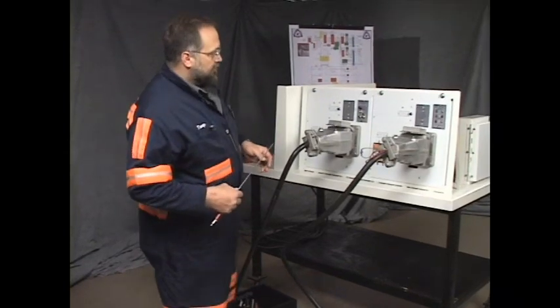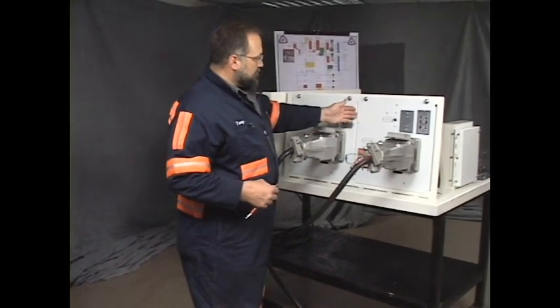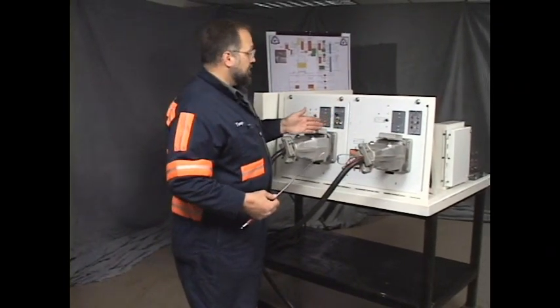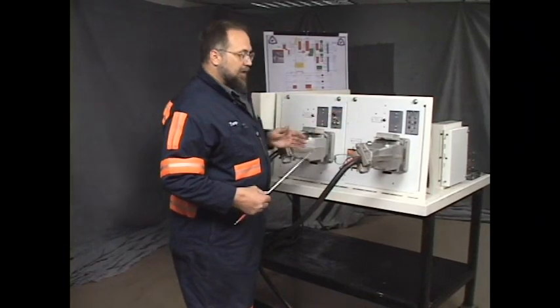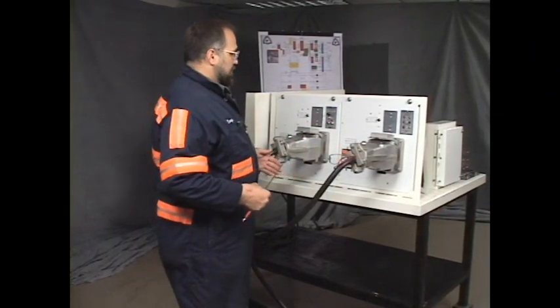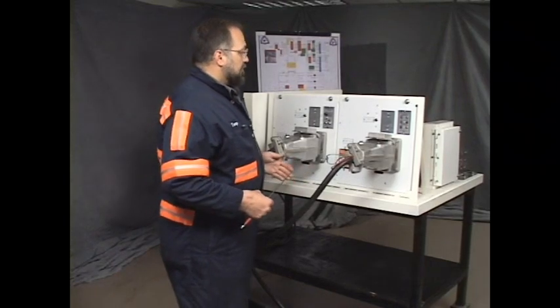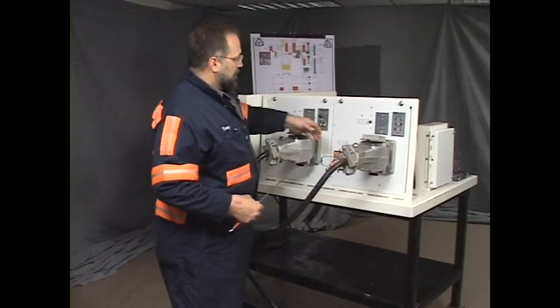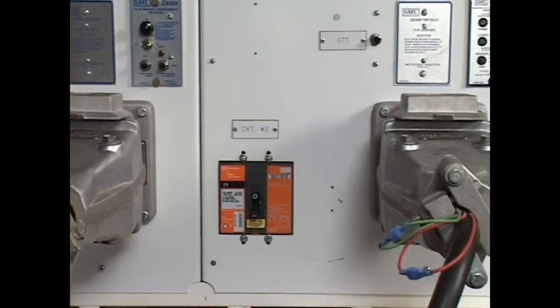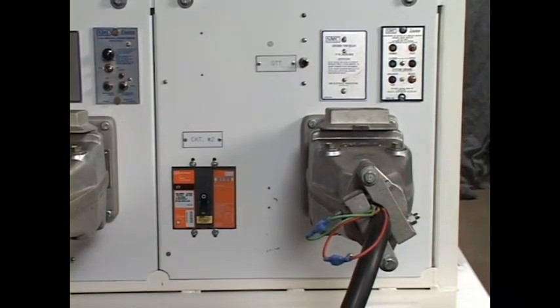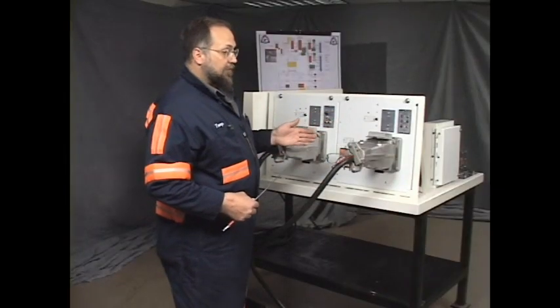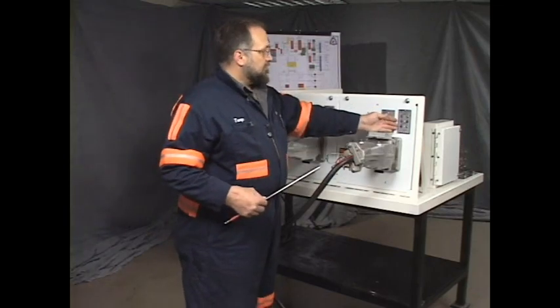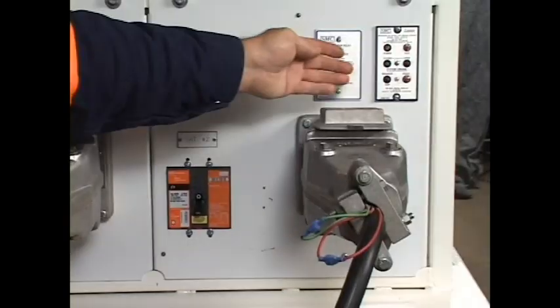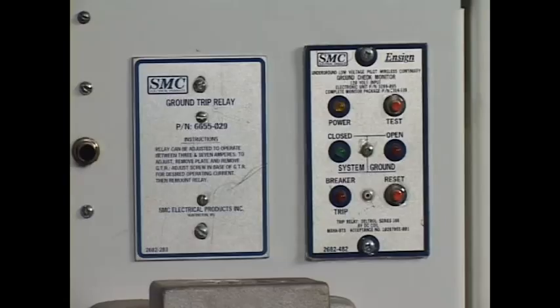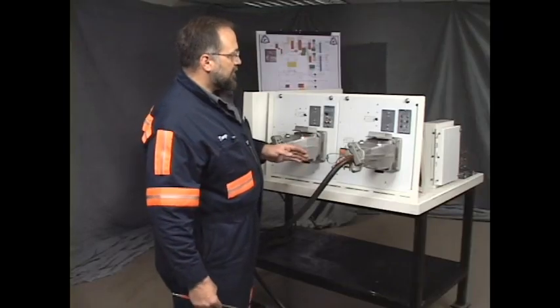Over here we have circuit number 2. For the main part, they are alike. Circuit number 2 is a module powered by the same source, but it supplies a separate circuit, and it's operated independently of circuit number 1. It has a circuit breaker for circuit 2. Has a ground trip test switch that you would test the ground fault. This monitor, as you can see, is somewhat different. This is the wireless monitor that we spoke of earlier. Audio monitor, tone monitor. They all mean the same thing.